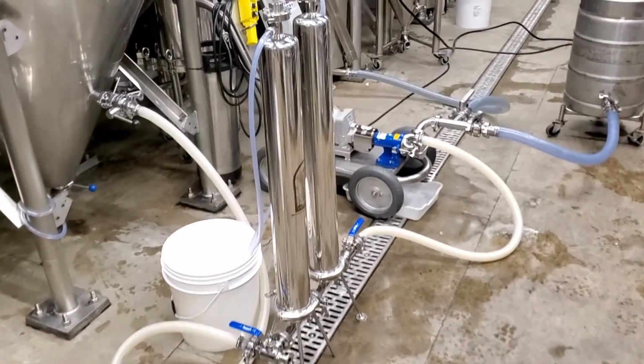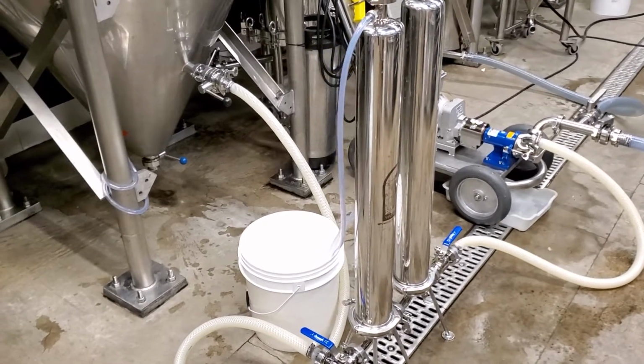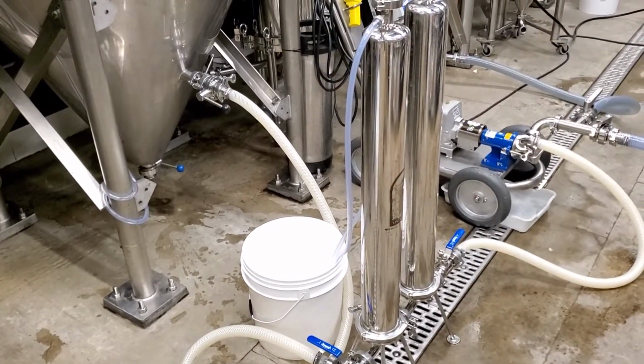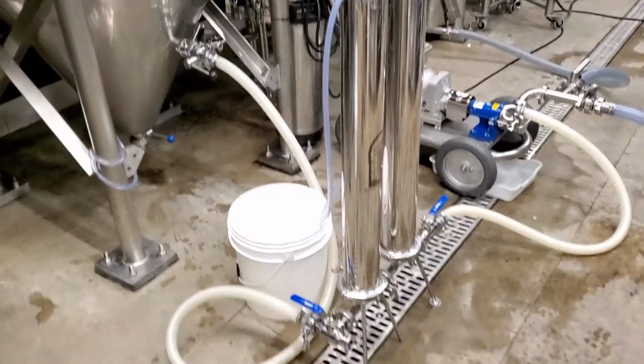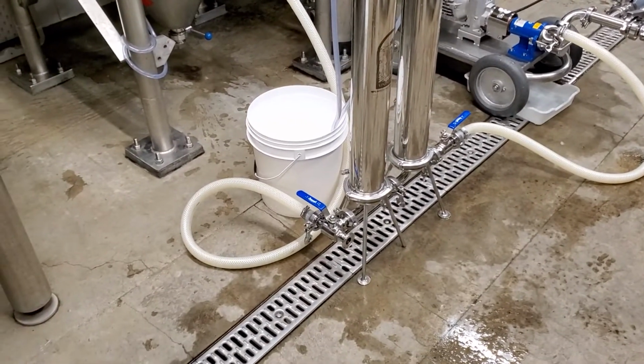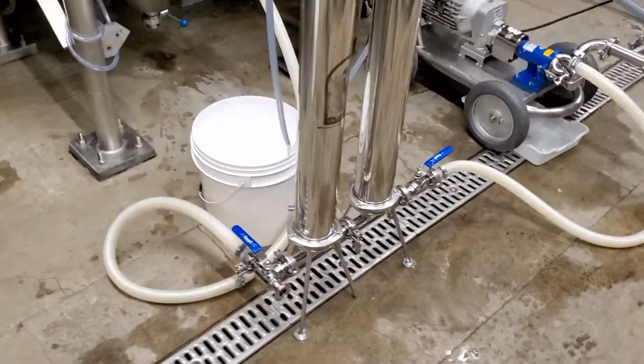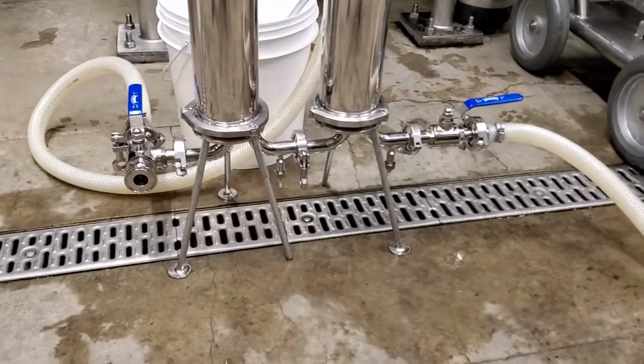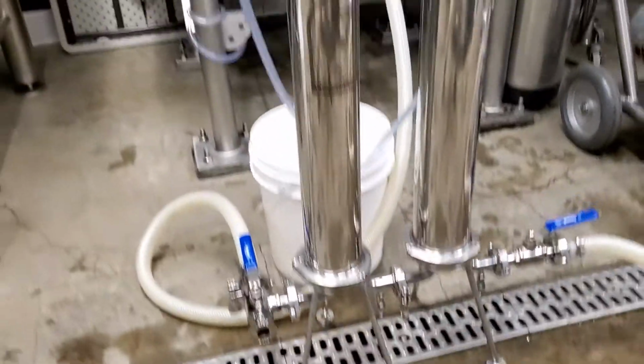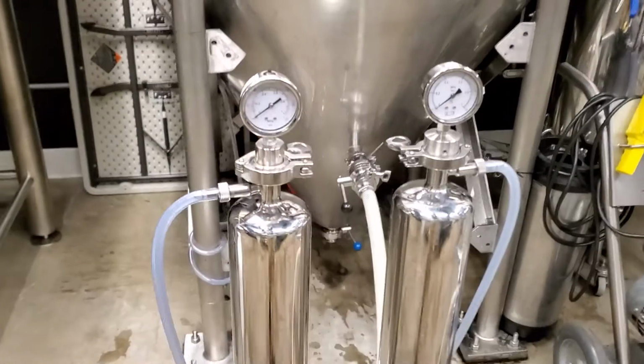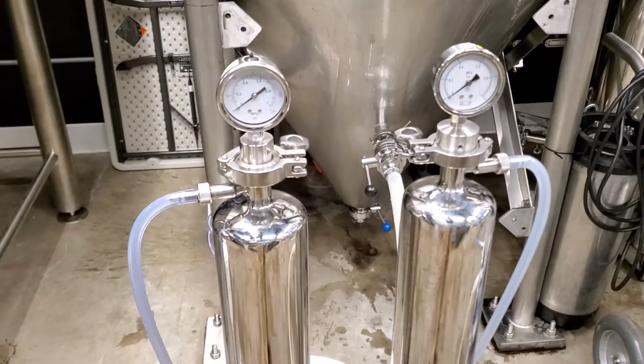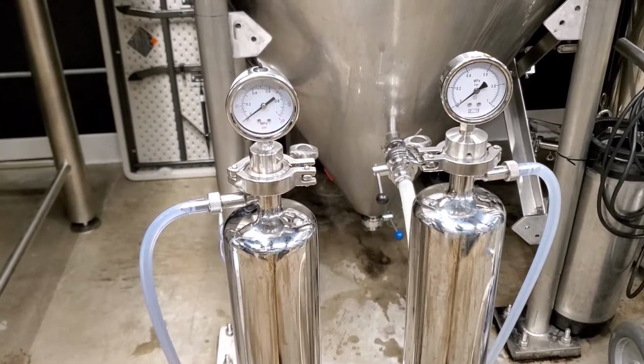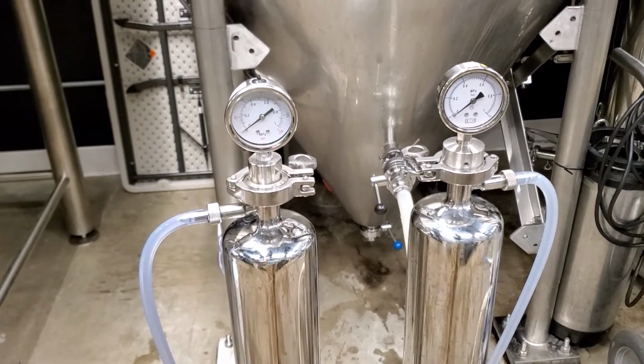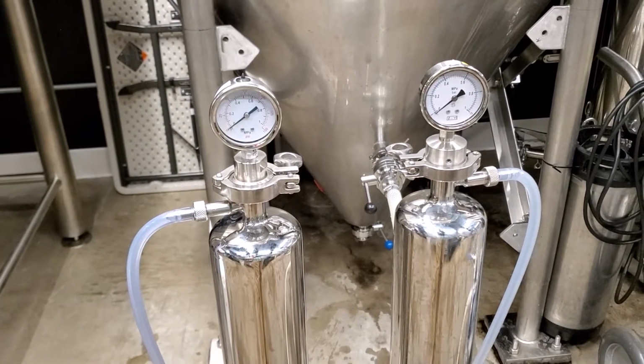We have walked through our entire outlet side of the cartridge filters. The racking arm on the tank is open. Our T valve is oriented in the right direction. We have both the little dump valves at the bottom closed. Up at the top of the cartridge filters, we have both of these redirect valves open just slightly so that we can make sure the chambers are full.